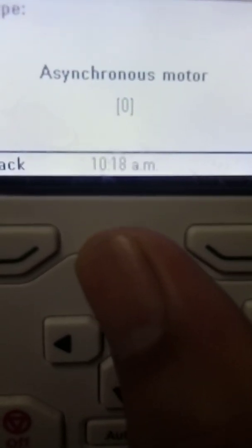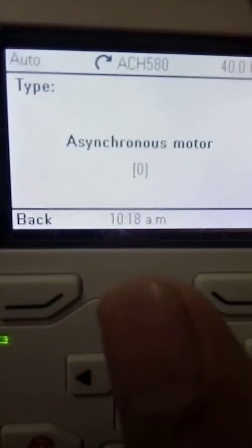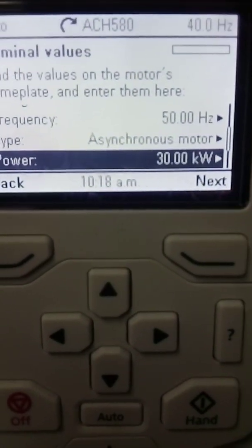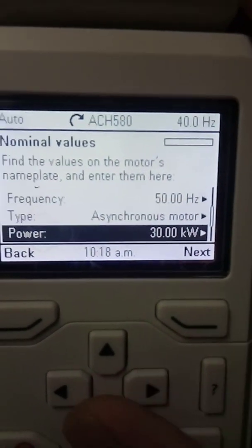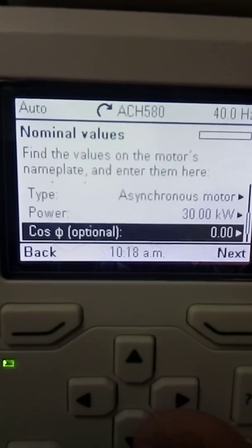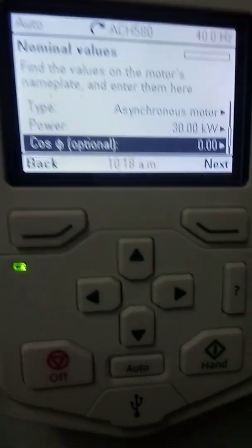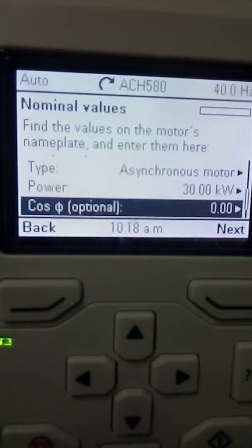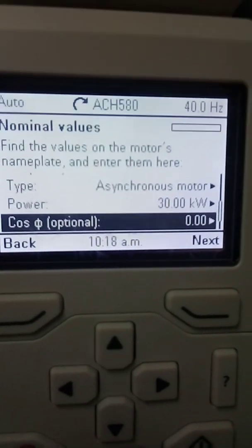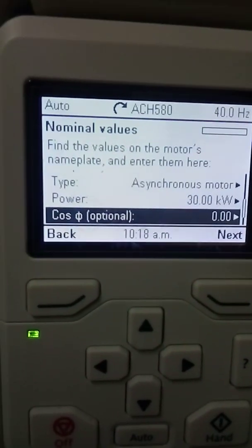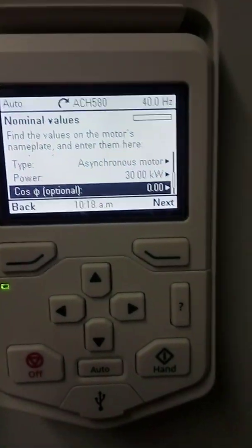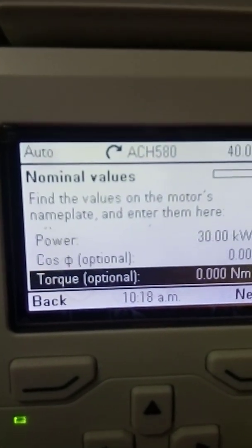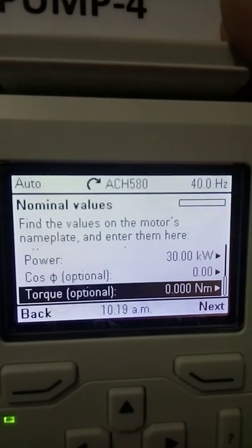As you can see it's zero — currently my drive is locked. You have to choose your motor type. For power, my motor is 30 kilowatt, so I have put that value. You have to check your motor nameplate and feed the value. The next parameter asks for the power factor of your motor — again check the nameplate. This value is not critical; if you don't feed it, your motor will still run at the correct speed. But the most important parameters are voltage, current, and speed — those three are essential, along with the power.